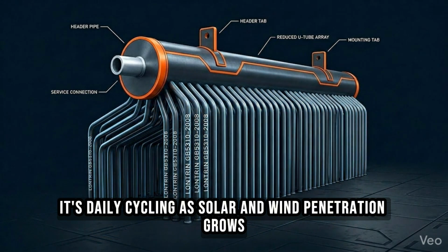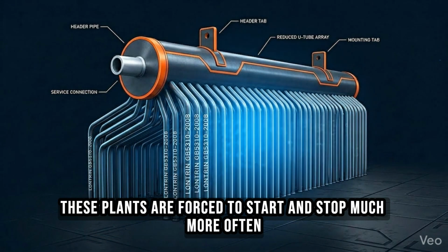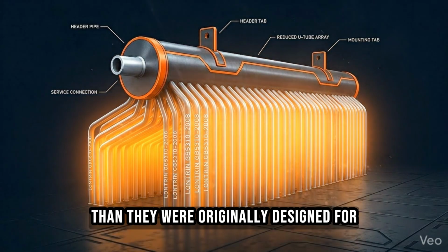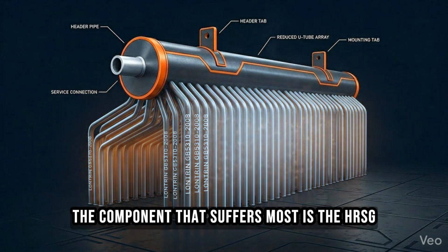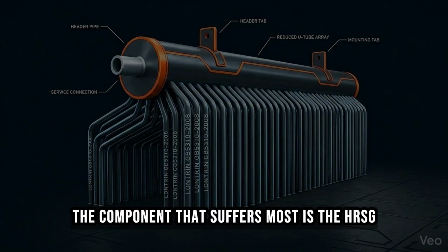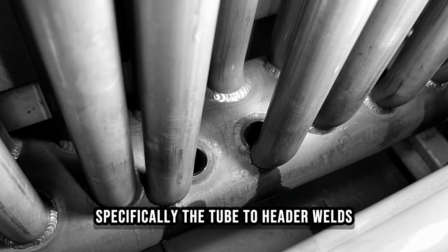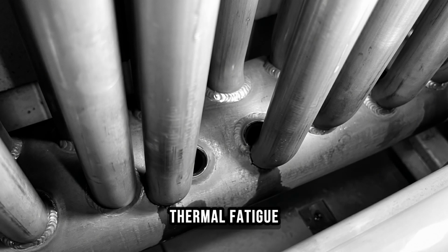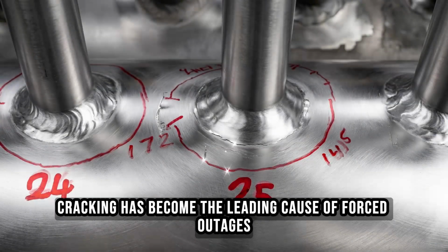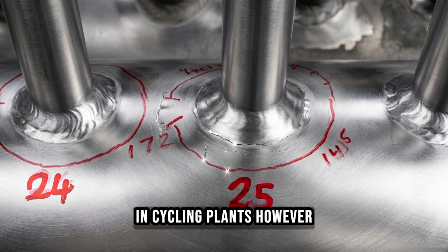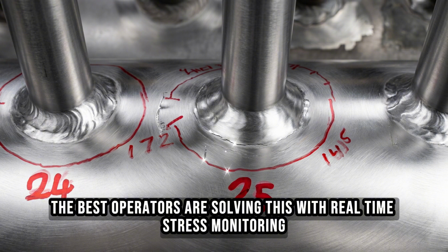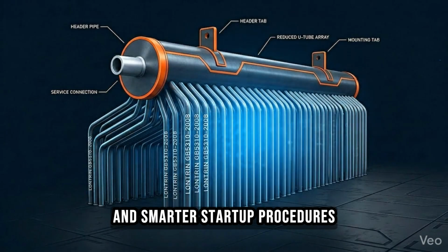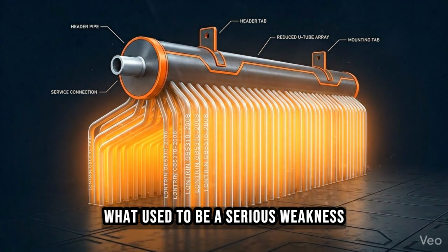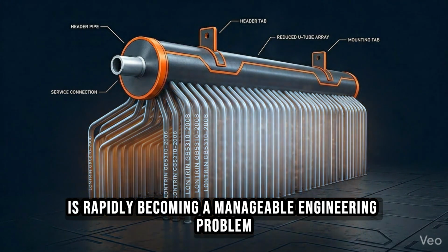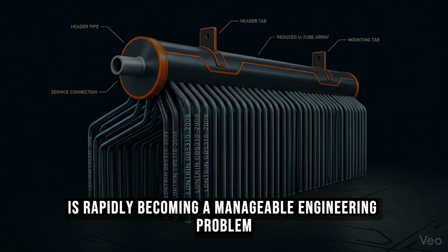As solar and wind penetration grows, these plants are forced to start and stop much more often than they were originally designed for. The component that suffers most is the HRSG, specifically the tube-to-header welds. Thermal fatigue cracking has become the leading cause of forced outages in cycling plants. However, the best operators are solving this with real-time stress monitoring and smarter startup procedures. What used to be a serious weakness is rapidly becoming a manageable engineering problem.